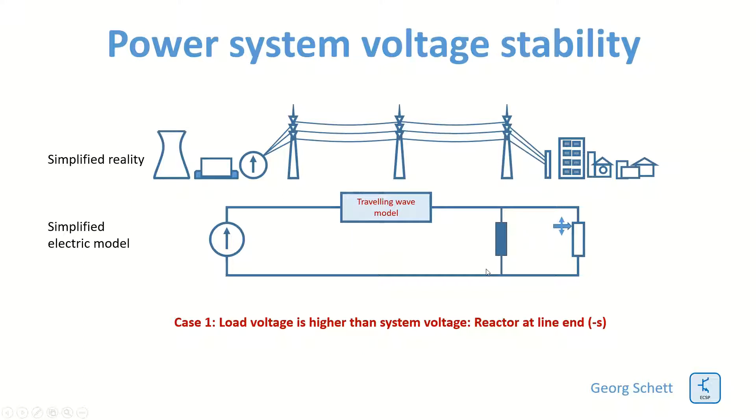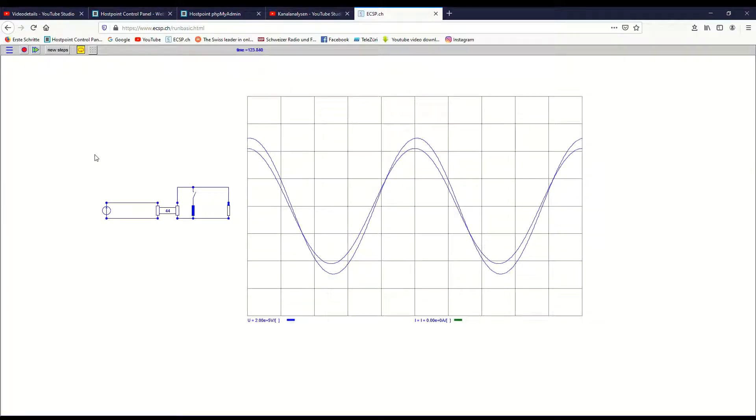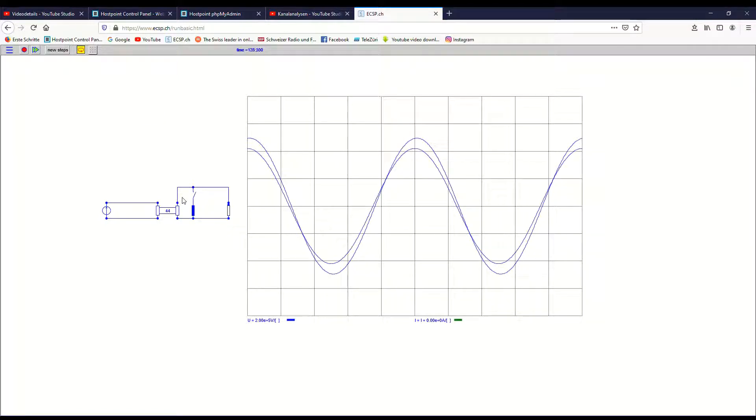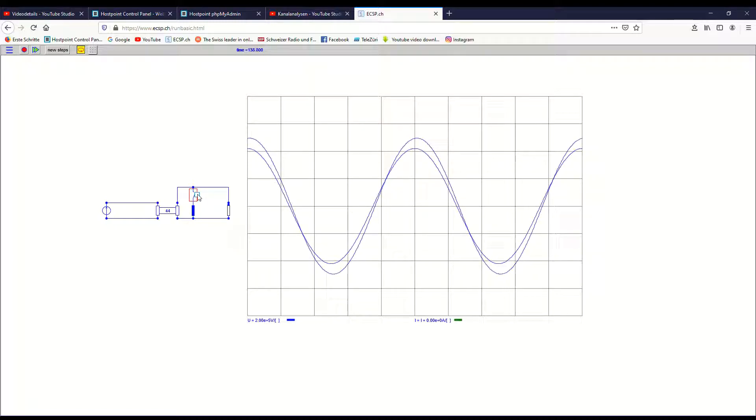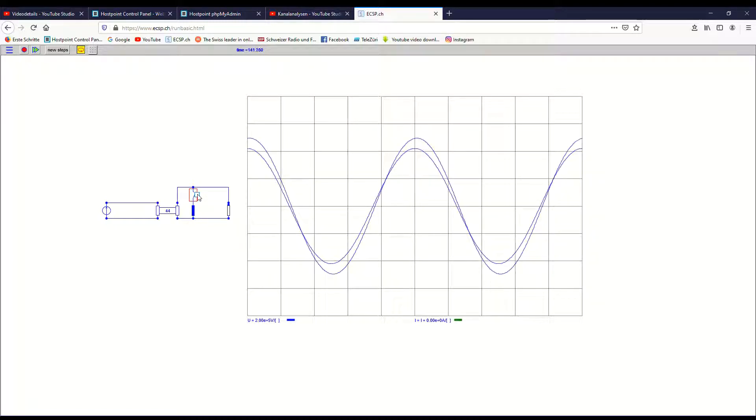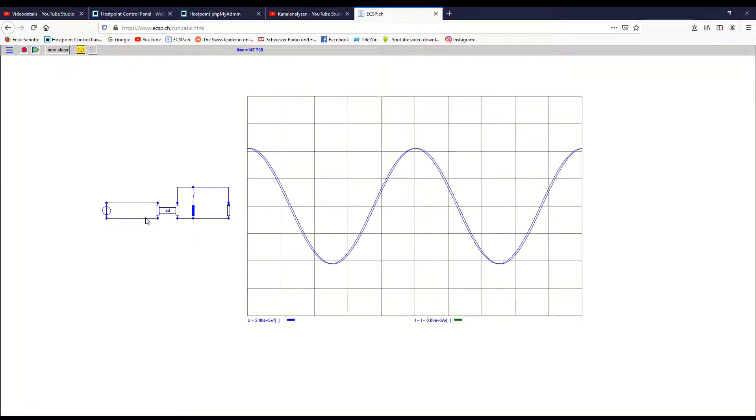We can also put the reactor at both line ends. I have now added a reactor at one of the line ends, and I will now switch on this reactor and look at what happens on the voltage curve. You see that switching on or off, the voltage at the line end is compensating for the capacitive surplus reactive power in the line.